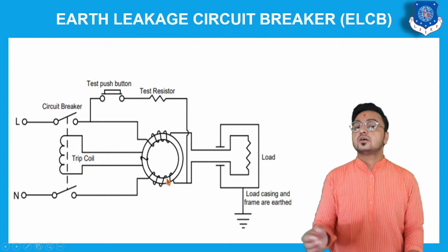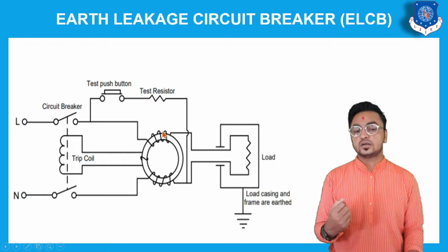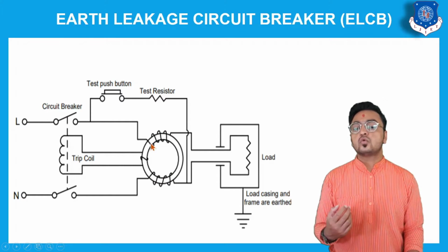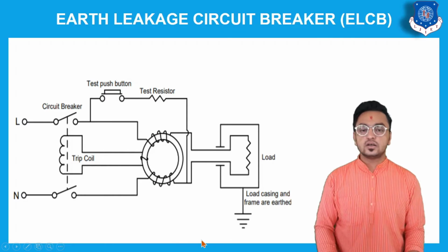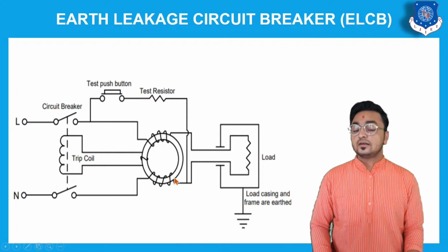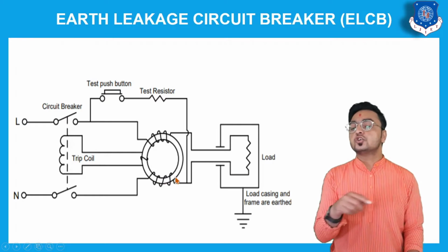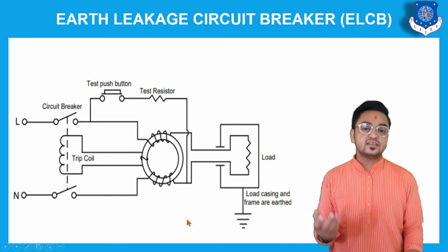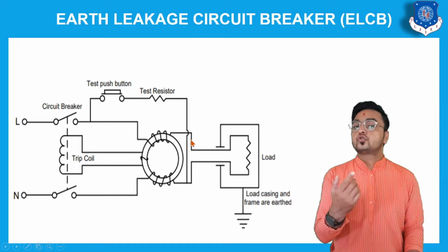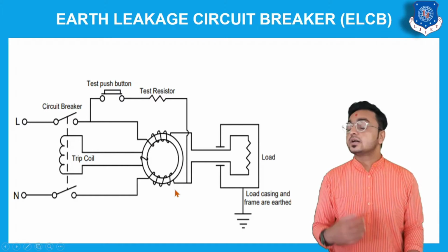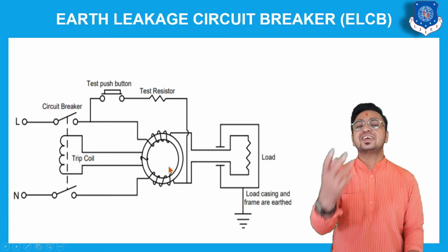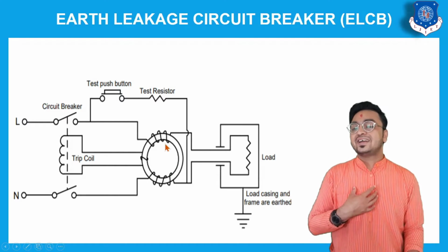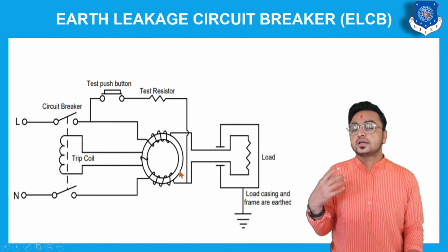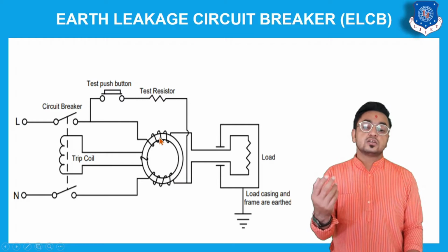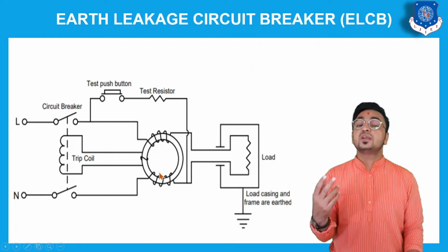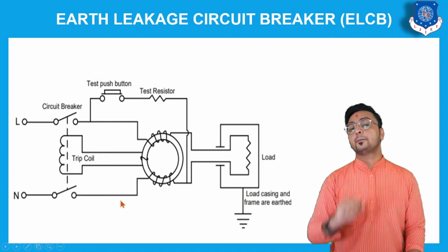We have another identical coil, connected in the neutral or return path. Both coils are identical. In normal condition, both coils have the same current, and because of that both generate the same magnetic flux. We arranged it so the two fluxes of these coils are in opposite directions compared to each other.